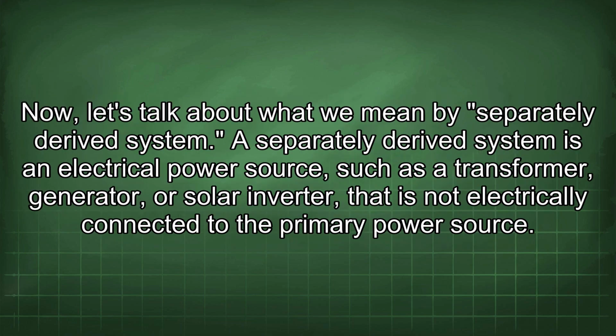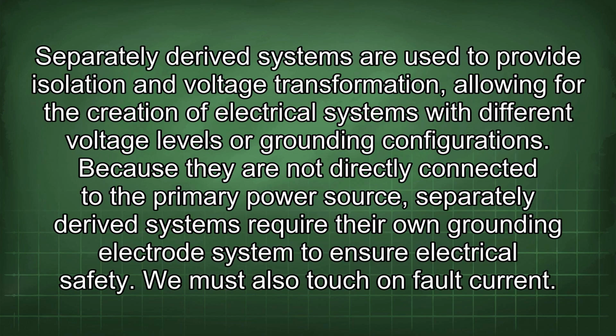grounding. Now let's talk about what we mean by separately derived system. A separately derived system is an electrical power source such as a transformer, generator, or solar inverter that is not electrically connected to the primary power source. Separately derived systems are used to provide isolation and voltage transformation, allowing for the creation of electrical systems with different voltage levels or grounding configurations. Because they are not directly connected to the primary power source, separately derived systems require their own grounding electrode system to ensure electrical safety. We must also touch on fault current.